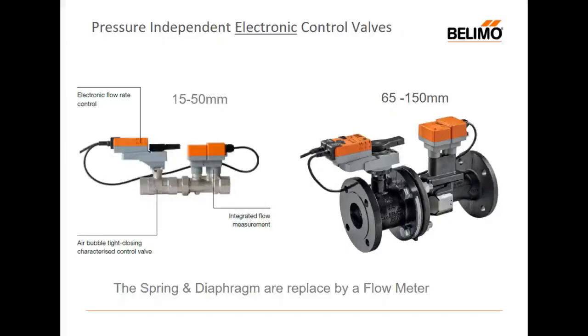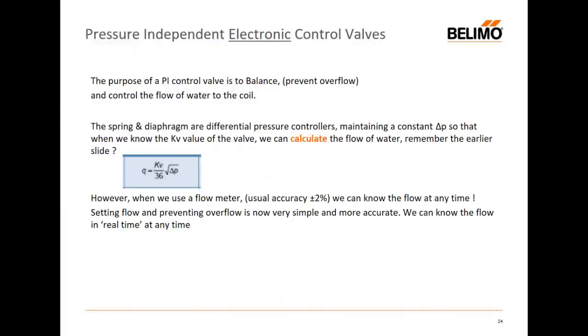And the reason that we have a spring and a diaphragm in the mechanical type is that we calculate, and we saw the calculation, we calculate the differential pressure using the KV value, mechanically trying to maintain a constant delta P in order to calculate the flow. And if we want to know the flow, my company is taking the view, well, just measure it, because that really is the best way. If you want to control something, it's best to understand it. And the best way to understand it is to measure it. So the pressure independent control valves are designed to balance by preventing overflow automatically and then able to control the flow of water to the coil. The spring and the diaphragm are no longer required. That's been replaced by an actual ultrasonic flow meter.